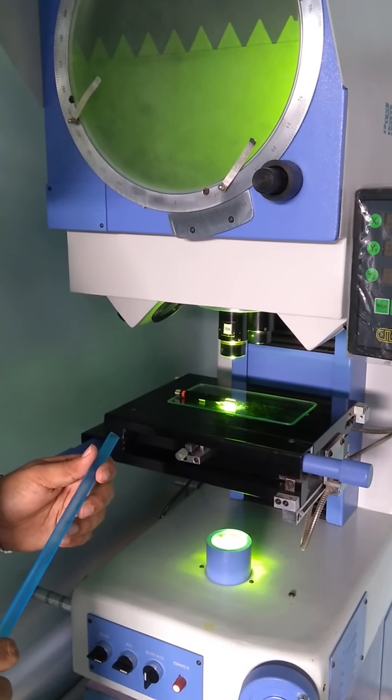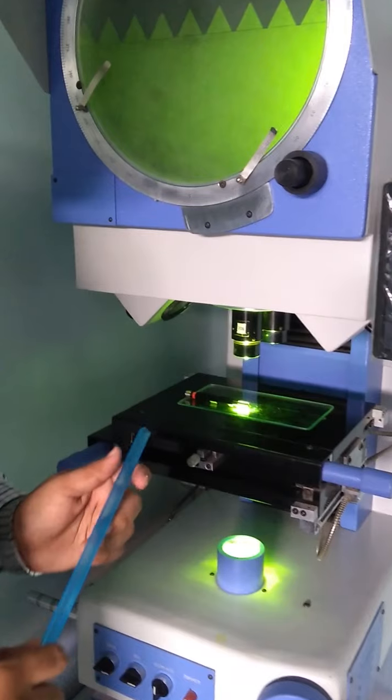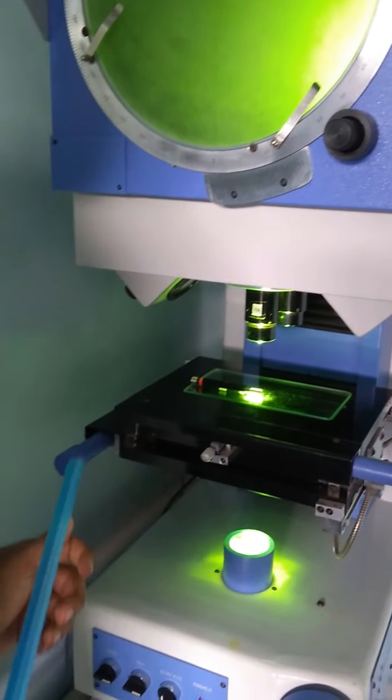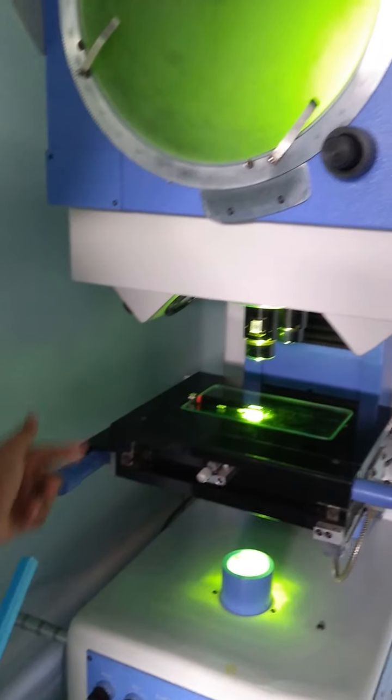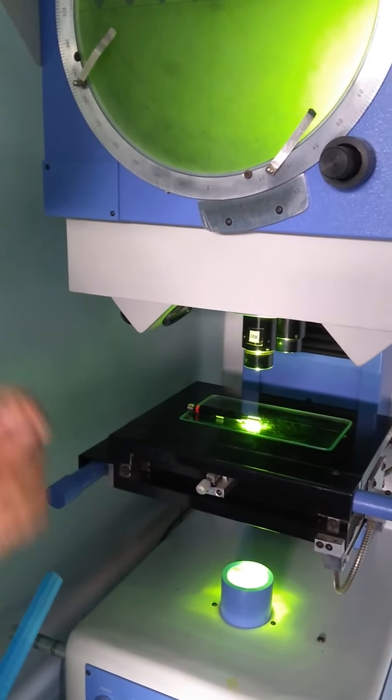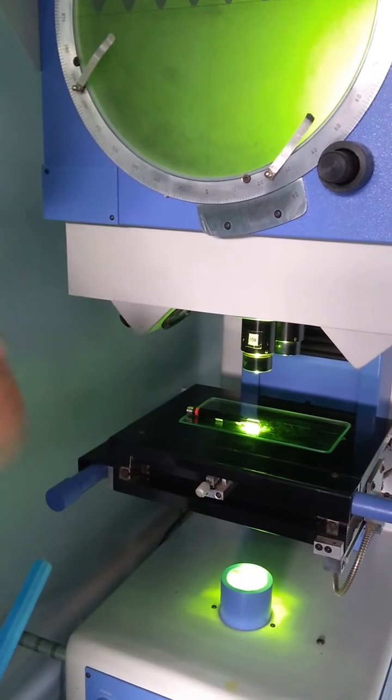The working of the profile projector. We have placed the screw profile here whose parameters are to be measured. As I said earlier we will be moving the platform both vertically and horizontally to measure the depth, major diameter, minor diameter and pitch of the given profile.